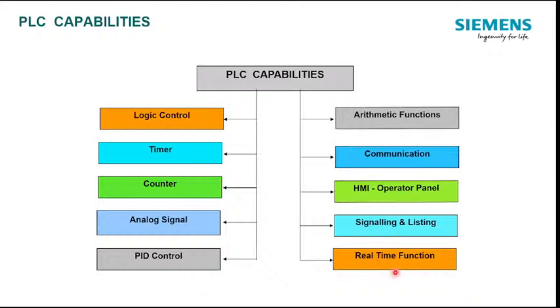Real-time functions like date and time. For example, instead of me going and pressing the start push button or switching on the machine remotely through HMI, I can write a logic in PLC in such a way that every day morning 9 o'clock, my V1 will get open. So my process will start running continuously. So that kind of time and date or real-time functions we can also use in PLC.